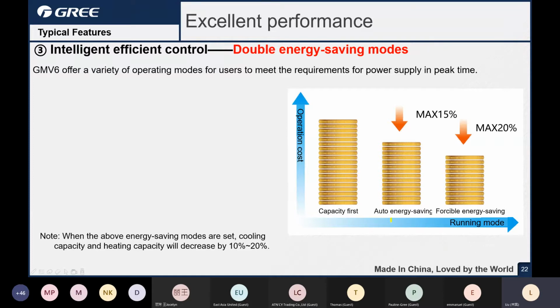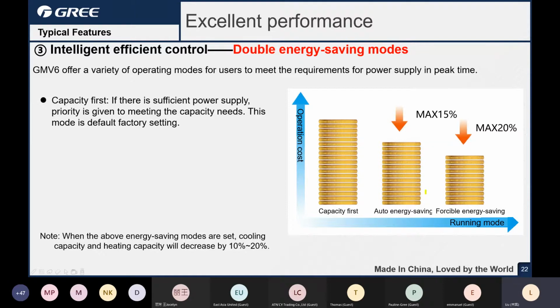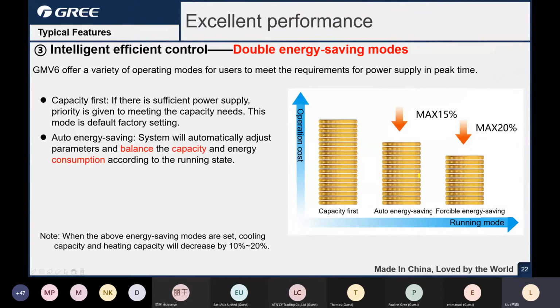And for the auto unit running, there are three different choices. The first one is capacity first. That means don't consider the noise, don't consider any limitation, don't consider anything, just maximize your output, maximize your capacity. Okay, another one, that's auto energy saving. This energy saving can balance the capacity and the power consumption, depending on the running state. So the maximum you can get is around 15% energy saving.